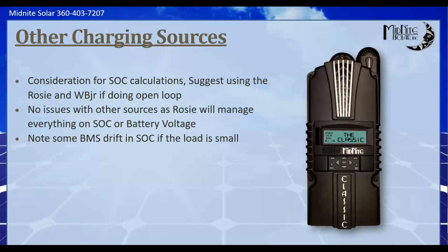So let's say you have 4 of our PowerFlow 5 batteries, and you're a real power miser, only drawing 150 watts through the night. That 150 watts probably isn't enough for those 4 batteries to recognize, and they will not actually drop their state of charge as you go through the night. Why I mention this is if you're running in like an LBX mode or something and you're using state of charge, you can actually get to a point where you run the battery into a low voltage situation and it shuts down when the BMS still thinks there's actual percentage of the battery left.